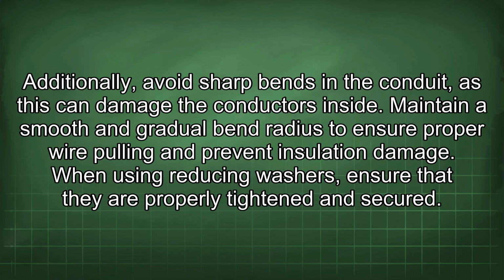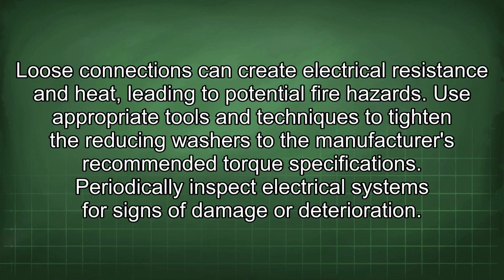When using reducing washers, ensure that they are properly tightened and secured. Loose connections can create electrical resistance and heat, leading to potential fire hazards. Use appropriate tools and techniques to tighten the reducing washers to the manufacturer's recommended torque specifications.